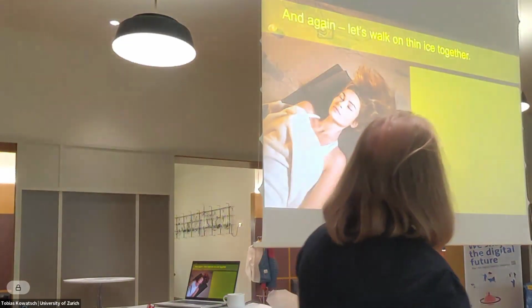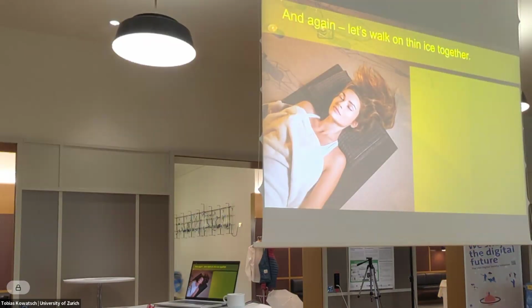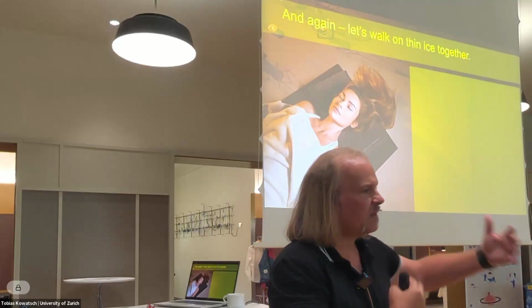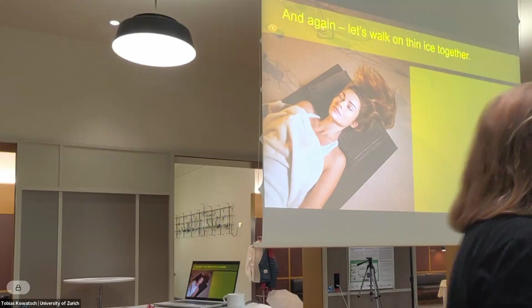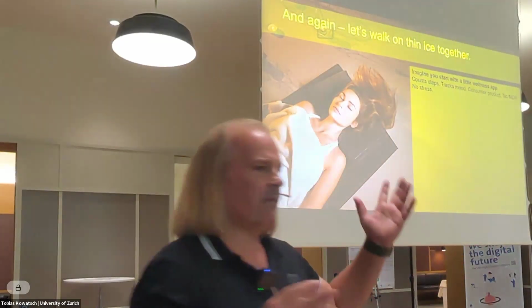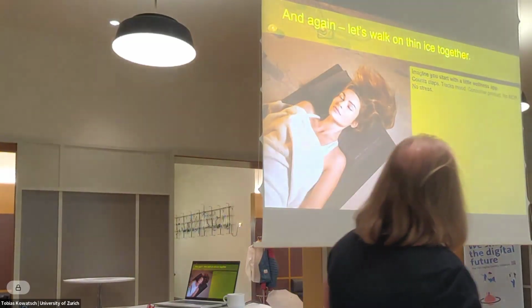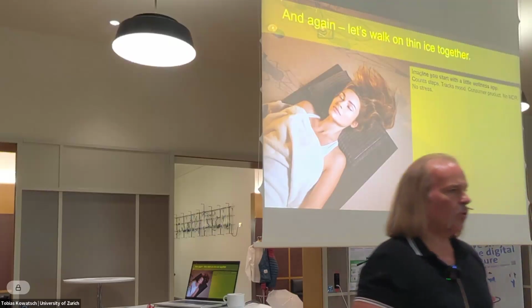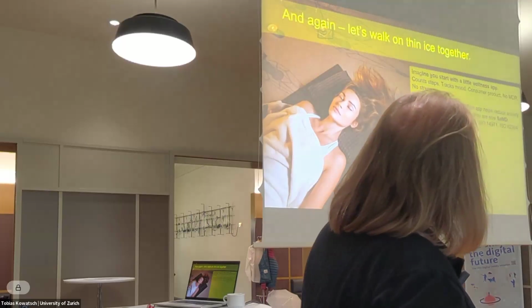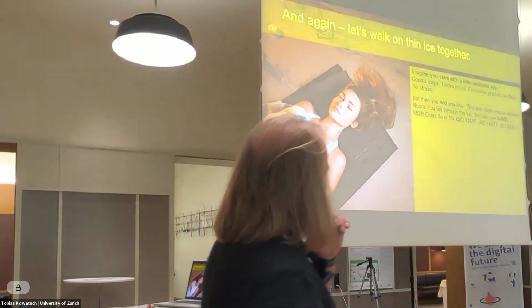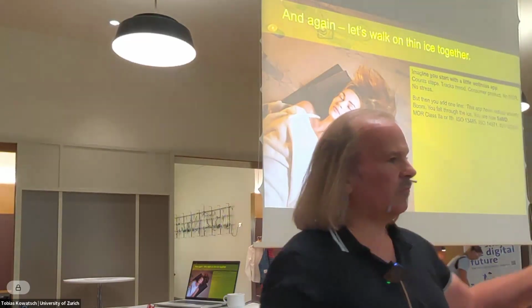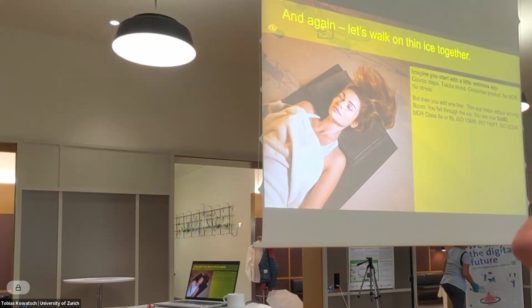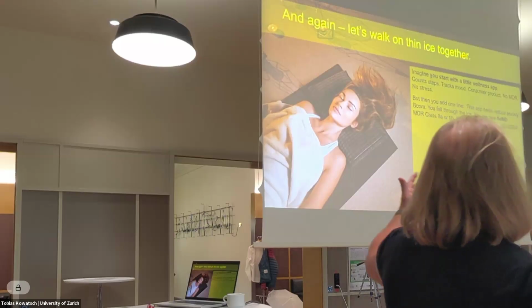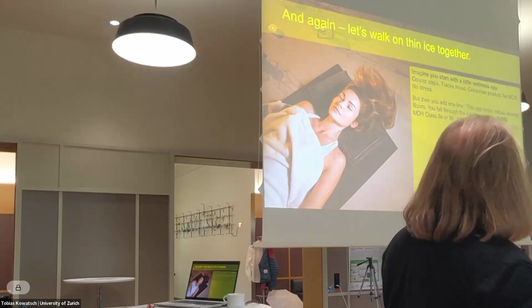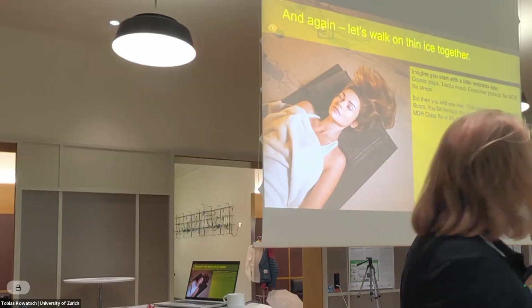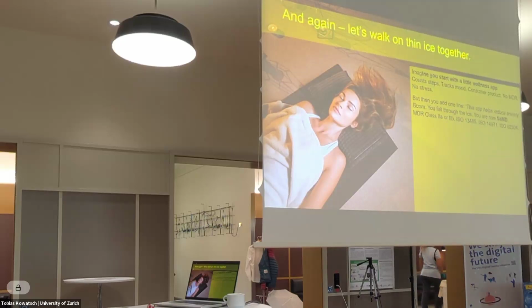And once again, let's walk on thin ice together, because this is the third thing that influences your classification or your success on the market. Imagine you start with a little wellness app. Count steps, tracks mood. It's a consumer product, no MDR, no stress, period. But then you add one line. This app helps to reduce anxiety. So you fall through the ice if you are not prepared for medical device regulation, because now you are a software as a medical device, classification 2A, maybe 2B. You have to respect ISO 13485 for quality management system, ISO 14971, ISO 62304, and all the other usual suspects.